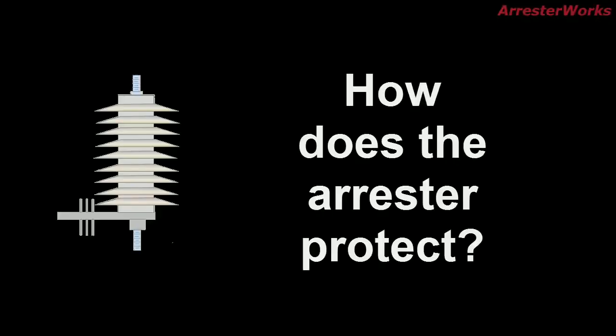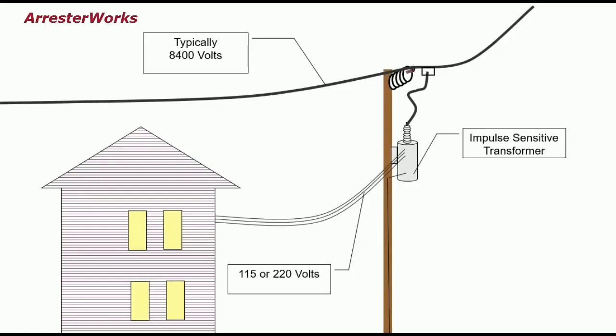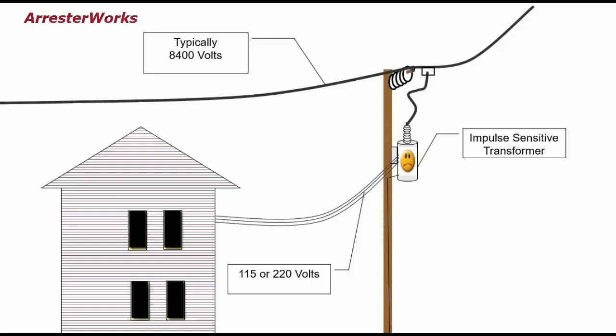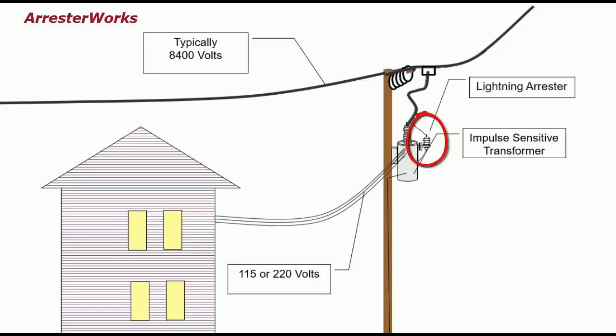So how does a Lightning Arrester protect the power system? Let's take a look at an example where the transformer is not protected by an arrester. If lightning were to strike the line, the current will flow down the line into the transformer. This will most likely result in damage to the transformer and the lights will go out. However, if the transformer is protected by an arrester and the line is hit by lightning, the arrester will turn on and divert the surge to ground. The arrester protects the transformer from damage and of course, the lights stay on.